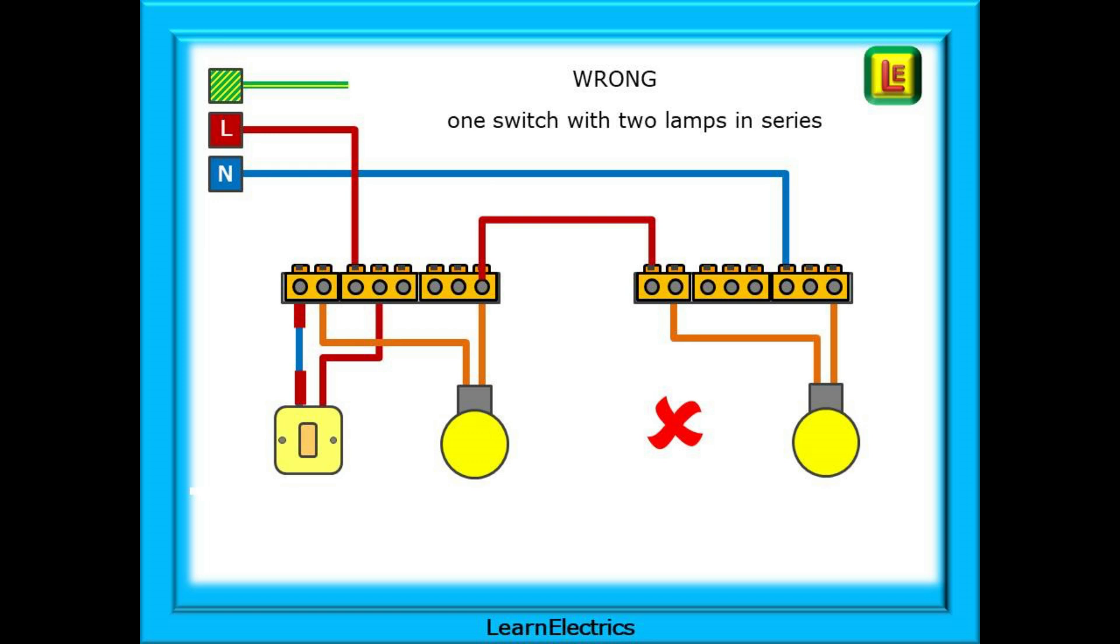Now, this is where it goes wrong. The first lamp is connected between the switch block and the neutral, but there is no neutral connection at the leftmost ceiling rose. Instead, there's a link to the switch block on the second ceiling rose, and then a neutral connection back to the consumer unit. This is now a series circuit. Two lamps in series across the 240 volts. Totally wrong.